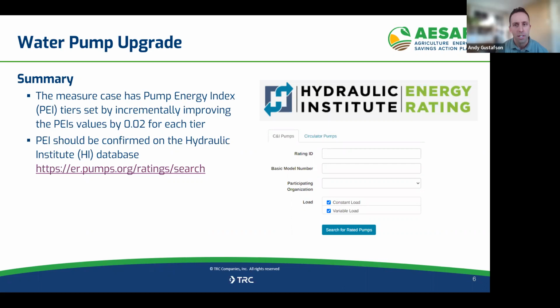So what's the pump energy index? The pump energy index is the energy demand relative to what a standard efficiency pump offering is considered. For example, a pump energy index value of 0.9 means it's consuming 90% of that standard pump comparison - using 10% less energy relative to it. So a 0.9 value represents 90% of what's considered the standard pump efficiency value or operation. There's a Hydraulic Institute energy rating website for this.